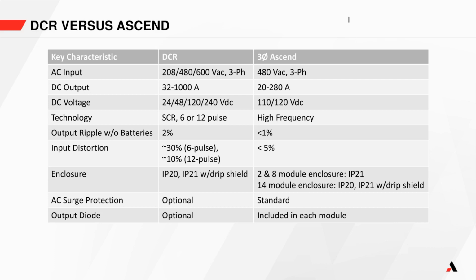On the Ascend, all 2 and 8 module enclosures are IP21 rated, and the 14 module enclosure is IP20 rated, but it can be IP21 rated with a drip shield. We have standard AC surge protection on our Ascend charger, and each module has an output diode, whereas on the DCR charger, you just had one output diode for the entire system.